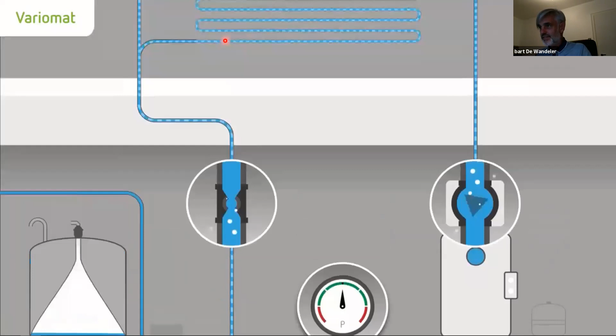If the pressure goes down, then it means that we have to do the average, that we have to actually pump water back from the expansion tank to the system with the pump, to again stabilize the pressure in the system. This is the third stage. What we also can do when the system is heating, is running, we have the free air bubbles that are running and pending into the floor heating, cooling panels, whatever, or even the radiators above on the top, the highest equipment that is installed in your system.